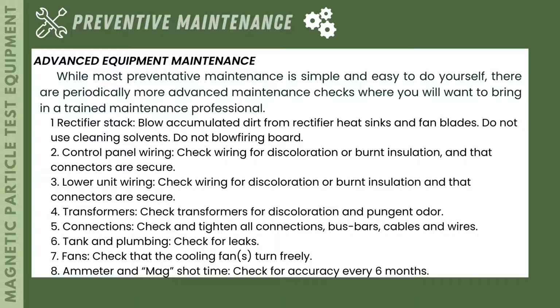For rectifier stack, blow accumulated dirt from rectifier heat sinks and fan blades. Do not use cleaning solvents. Do not blow the firing board. For control panel wiring, check wiring for discoloration or burnt insulation, and that connectors are secure. For lower unit wiring, check wiring for discoloration or burnt insulation, and that connectors are secure. For transformers, check transformers for discoloration and pungent odor. For connections, check and tighten all connections, bus bars, cables, and wires. For tank and plumbing, check for leaks. For fans, check that the cooling fans turn freely. For ammeter and magnetizing shot time, check for accuracy every 6 months.